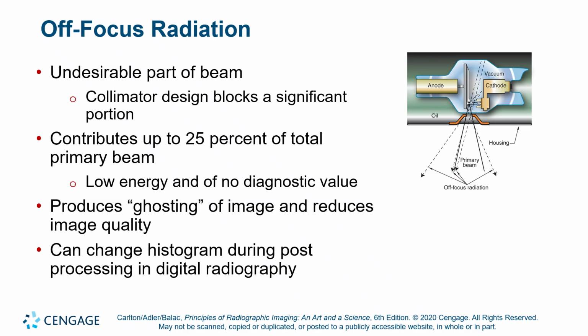If enough off-focus radiation hits the image receptor, it can produce some actual deposition of a significant amount of photons outside the collimation on our image receptor, and then that can be misinterpreted by our software, fooling the software into believing that that's part of the anatomy that we want to optimally display. And so off-focus radiation can become a problem.